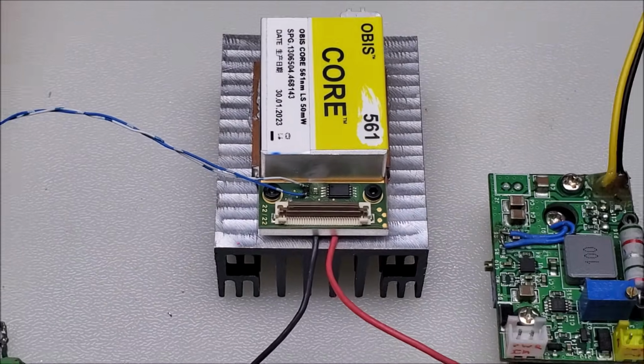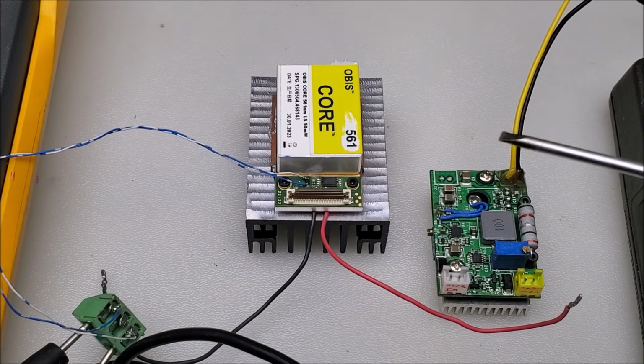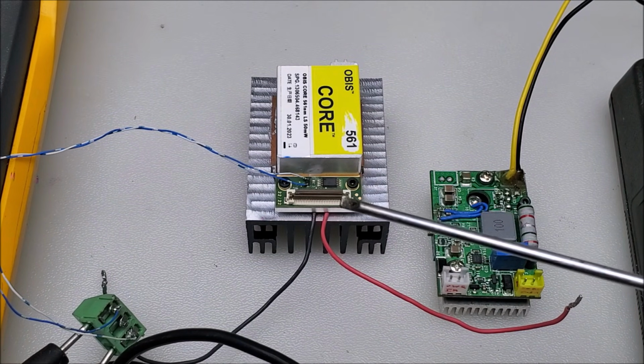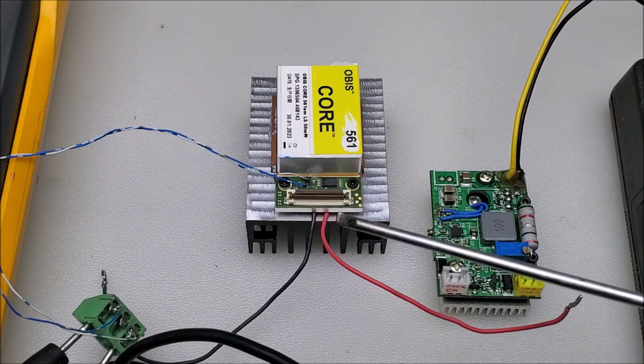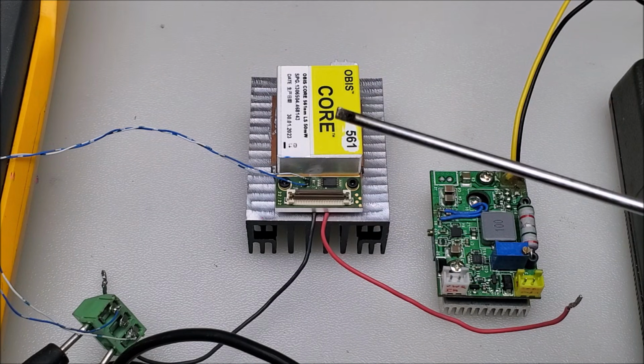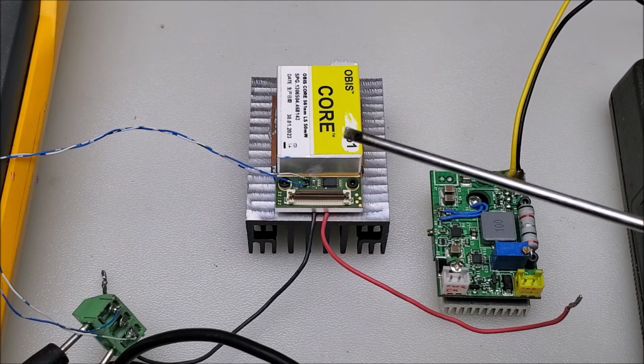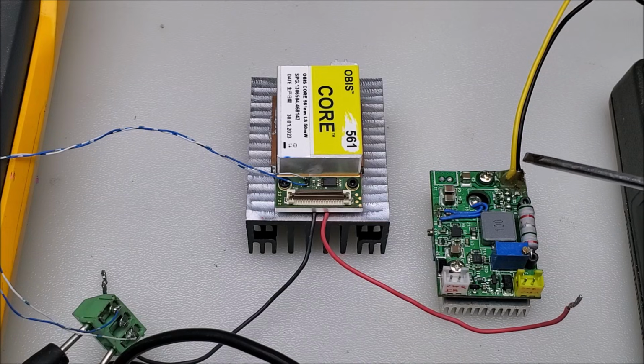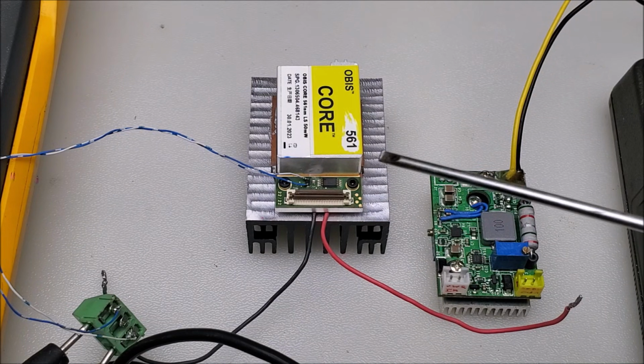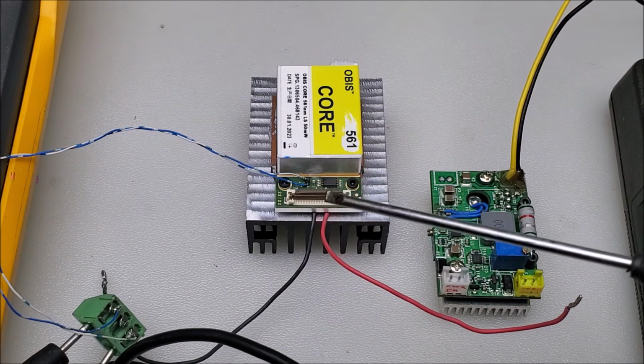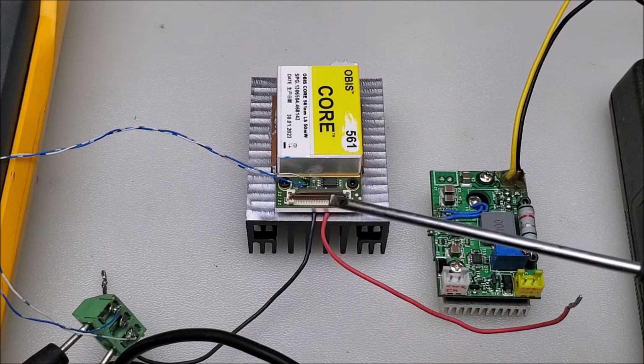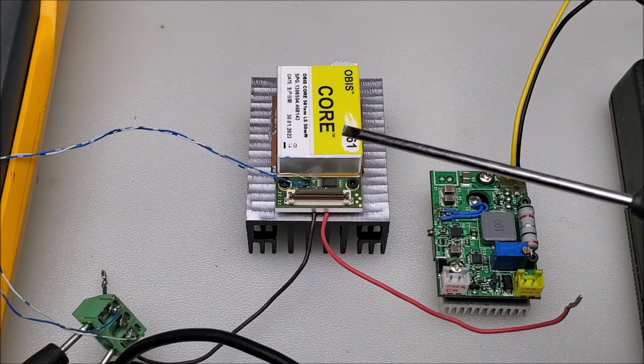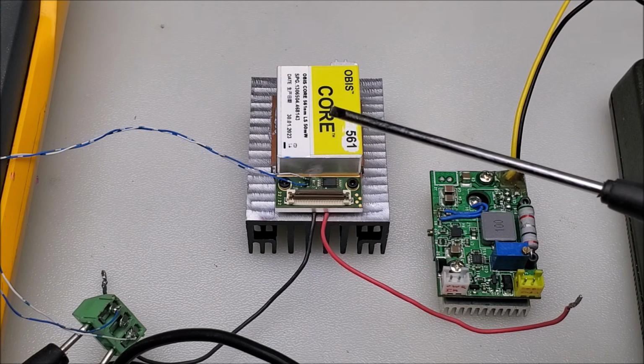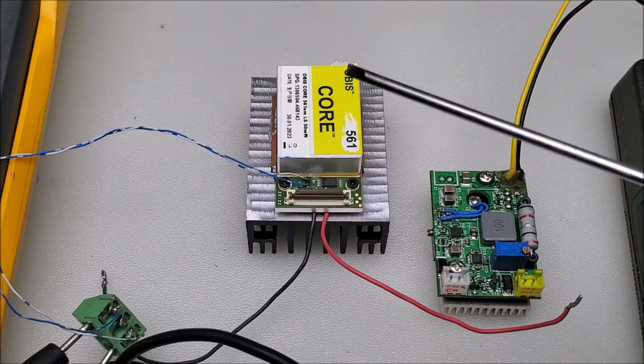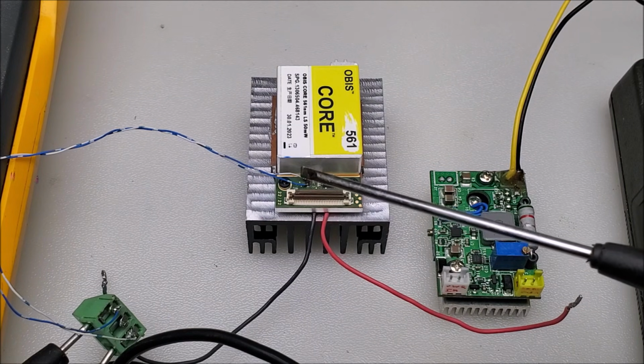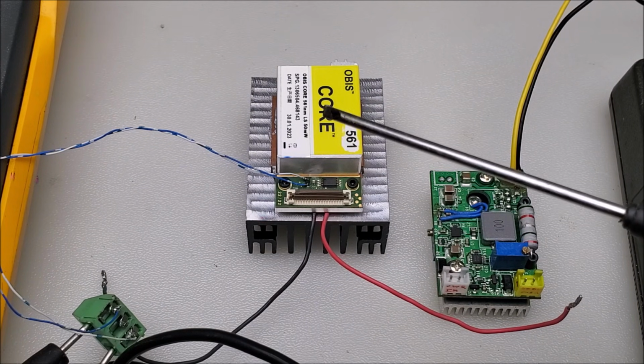The reason why I'm doing the reading there is because I want to avoid any kind of confusion with a voltage drop that might be present on the cable. And what I mean by that is if this laser requires 2 volts and I'm doing my reading here, I might read 2 volts here. But as the power goes through the cable, some of it might be used in that cable and the voltage might drop. And I might say get only 1.5 volts here. So to minimize that confusion, I'm going to do my reading as close to the Pump Laser Diode as possible.